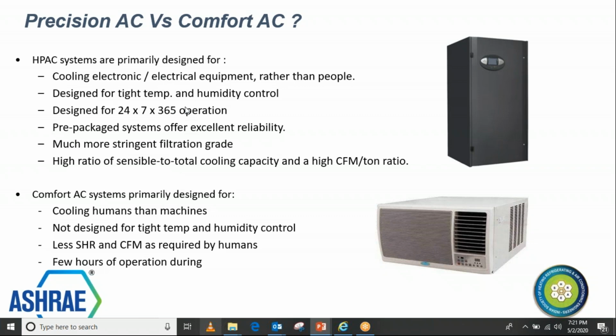The design of the cooling system matters because all these applications demand 24-hour, 365-day operation. So you cannot switch off the air conditioning system when you go home, because your control room, your data center, your server rooms, your hub rooms, or your other applications which support 24-hour operations are supposed to run continuously. You are not supposed to switch them off, unlike when you are at home or in office and you go out and switch off your air conditioner. So it is completely the reverse. It is supposed to run 24 hours, not 8 to 10 hours.